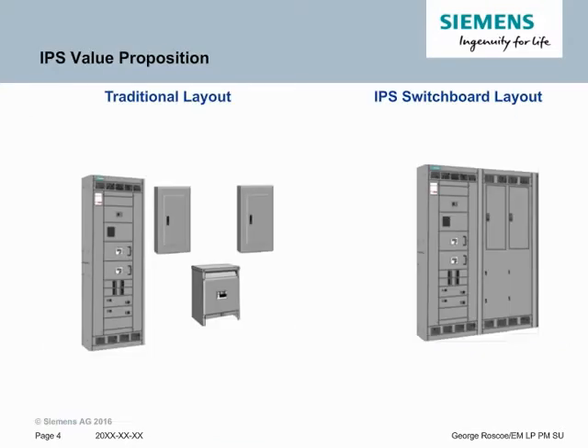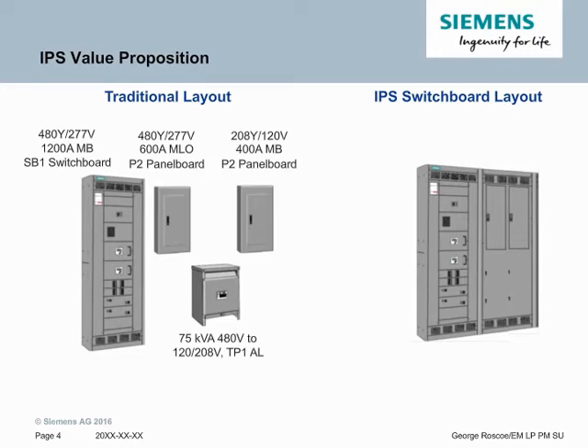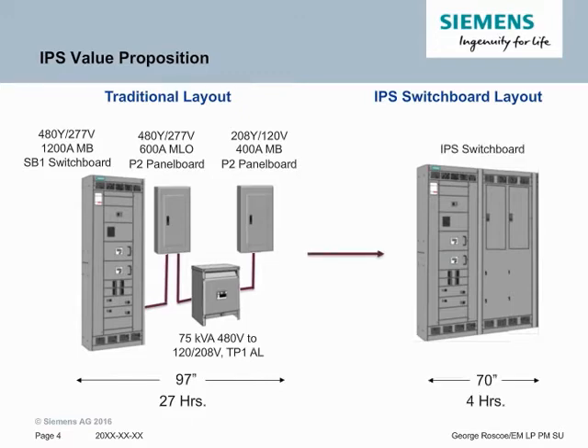In addition to floor space, one of the key value propositions is the total dollars you need to spend on an IPS switchboard versus a traditional layout. Take this traditional layout where you have a switchboard distribution section, 2 P2 panel boards, and the second panel board is fed by a 75 kVA transformer. All these require installation time and floor space. The time to install is about 27 hours. The IPS switchboard takes 4 hours to wire and is also only 70 inches wide, so that's 30% less space and 85% less time. Does it cost more?